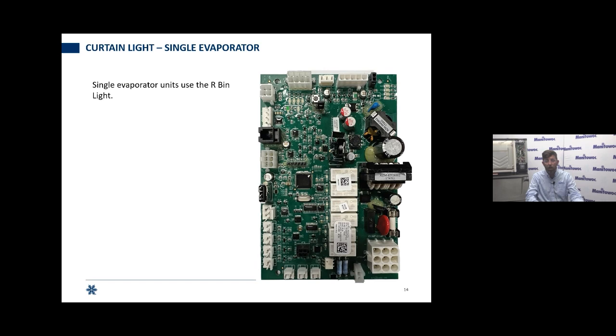So on a single evaporator ice machine, regardless of the number of circuits on that machine, just one plate, we're going to utilize the R bin light to call out that the curtain is closed. You'll see that light there. If the curtain, as it is behind me, is currently closed, that light would be lit. If that curtain came open, that light would turn off. Now, if you're suspecting an issue with that curtain switch, the magnetic bin switch, you're going to want to ohm that switch out. I've seen this light flash before when the curtain didn't move. So when in doubt, ohm it out.